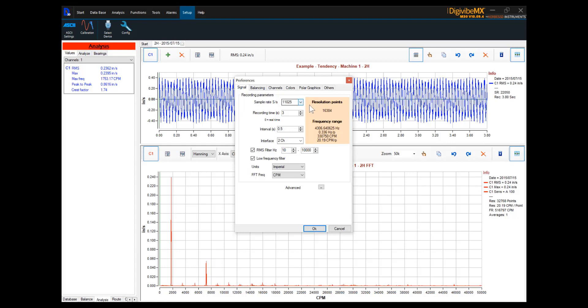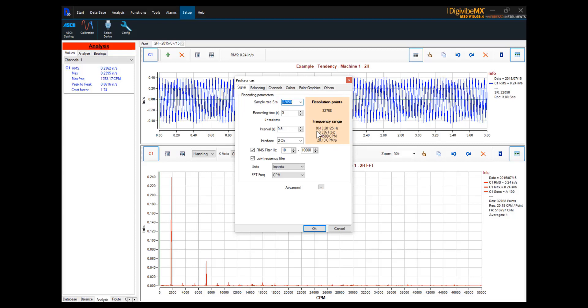As we see here, currently with 11,025 samples per second, we have a maximum frequency range of 4,306.640625 hertz within our frequency range, or 258,398.4375 cpm. If we increase our sample rate, basically doubling it to 22,050, we can see that the maximum frequency range of our FFT is now 8,613.28125 hertz, or 516,796.875 cpm.